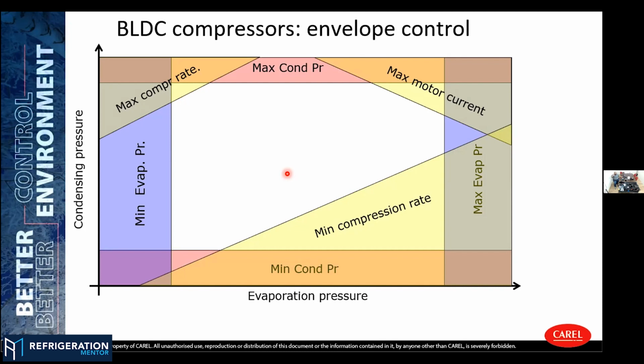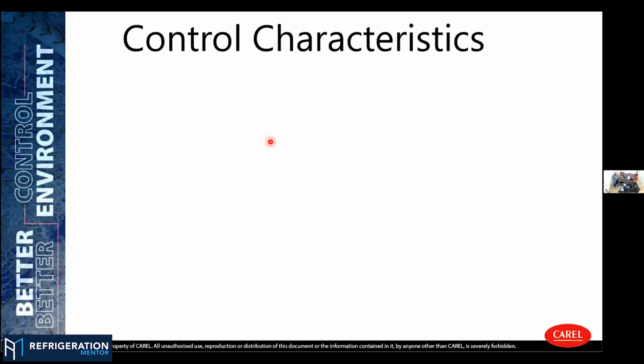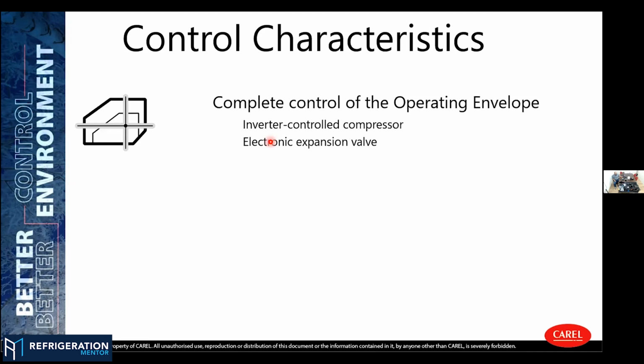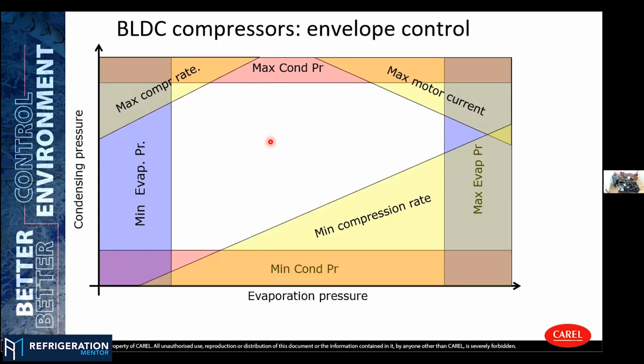And all of these things here in the middle, this white zone, is the main operation zone. This is where the compressor should work, let's say 99% of the time. This is the safest zone for the compressor to operate. But we may have some conditions where this could go bad, like the evaporator starts to frost too much, so the evaporation temperature in consequence starts to decrease, and we could come here. At this point, the compressor starts to decelerate in order to push the operation point back to the middle of the application.